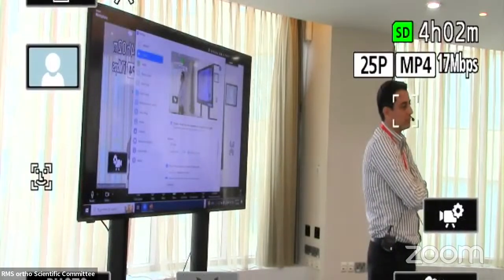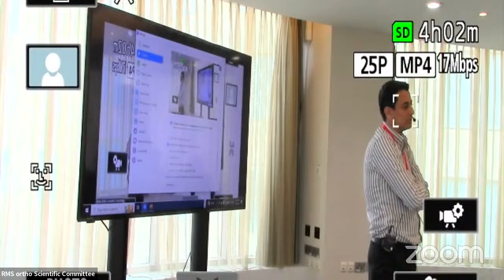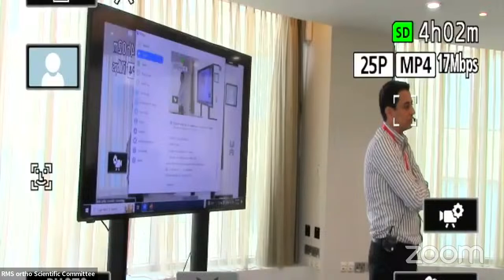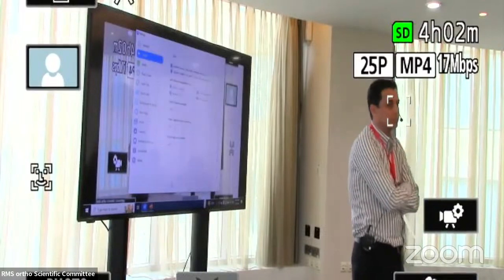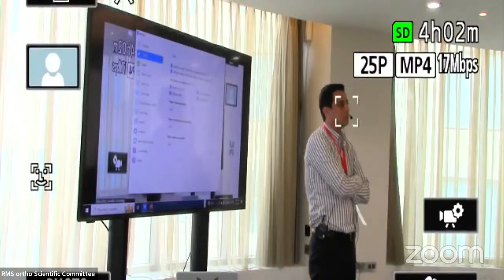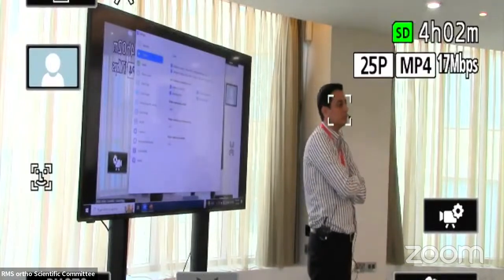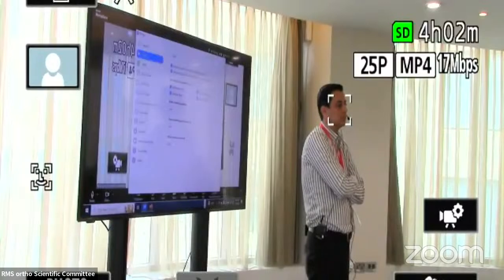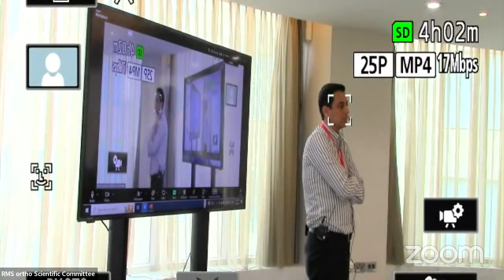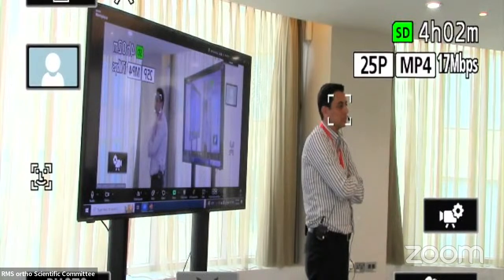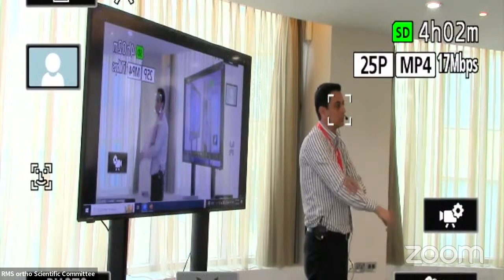As close as possible, and then you take the X-ray, you measure it on the X-ray, and then you make the changes. Exactly, the magnification. Because these radiology instruments need calibration, but you do it now.